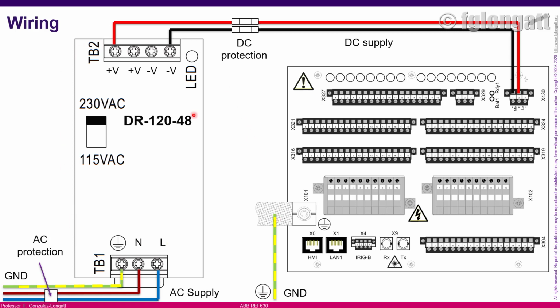Coming back to the power supply, this is the DC side, the DC supply for the IED, but on the bottom we need to connect to the AC grid. The line, represented here in blue color, is going to the power supply. Also we have the neutral, and in green and yellow we have the grounding. I have included overcurrent protection, for security, to protect against any malfunction or fault that can happen with this power supply. That is basically the connectivity we need in order to switch on the IED.